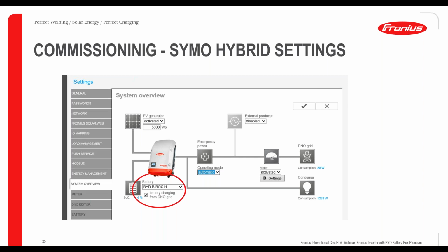Furthermore, you can select battery charging from DNO grid. This is not necessary to check, but it's good to check if you want to use further functions like the time of use functionality. With time of use, it's possible to charge the battery with energy from the public grid, so in case of cheap or nighttime tariffs, you can use this check button to enable charging from the DNO grid.